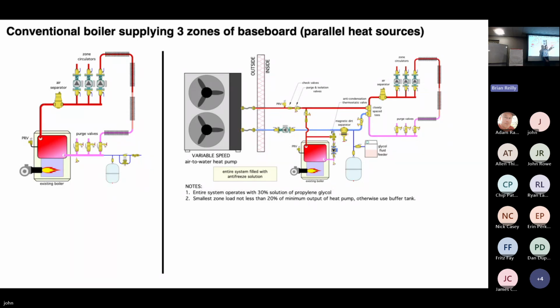And again, you see there's the pressure relief valve. Never set it up so the pressure relief valve is isolated from the heat source. Always make sure it can communicate. Same with the expansion tank. Make sure the expansion tank is always connected into the system so both heat sources can feel its presence there. So that's the modification of it.